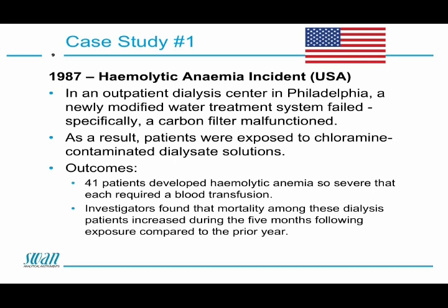As a result of this, patients were exposed to chloramine-contaminated dialysate solutions, and the outcome of that was that 41 patients developed hemolytic anemia, so severe that they each required a blood transfusion. Now, investigators found that the mortality among these dialysis patients increased during the 5 months following exposure compared to the prior year. So that was interesting to note.